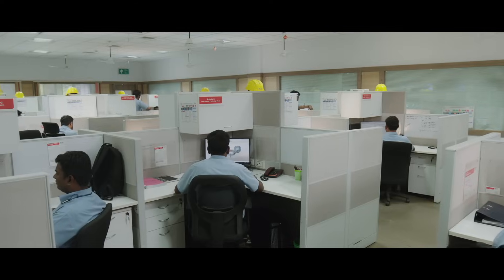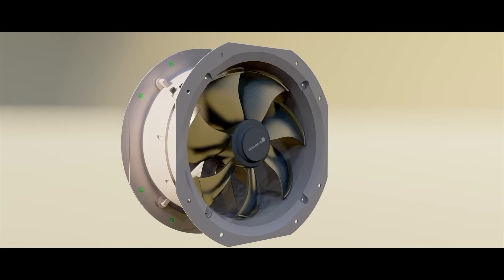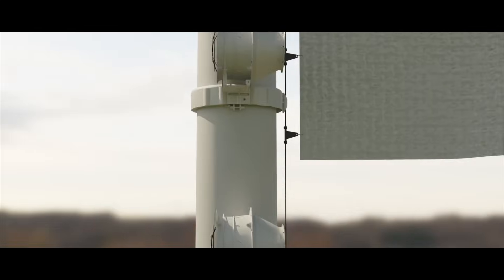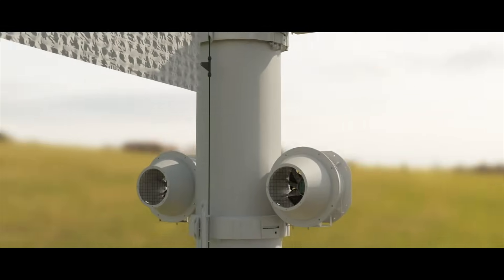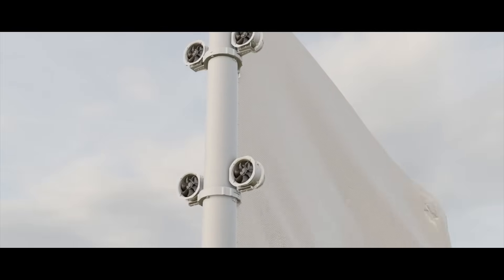The most important thing we needed were high-speed fans. We designed large fans with higher diameter which can throw air up to 50 feet. With 12 fans in tandem, we can create the breeze effect — around 30,000 CFM — which is necessary to keep the flag flying. These modules are positioned so that the first module is below the flag level; if the flag width is 60 feet, it starts at about 70 feet from the mast, aligned at an angle to provide lift. Then every 10 feet there are additional modules, and these six modules take care of the complete lifting.